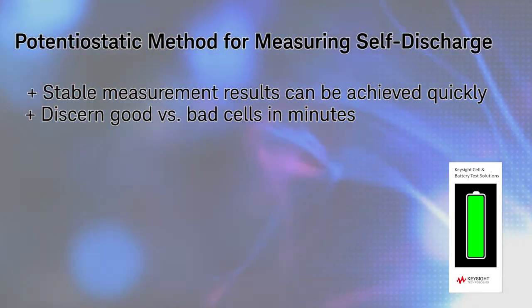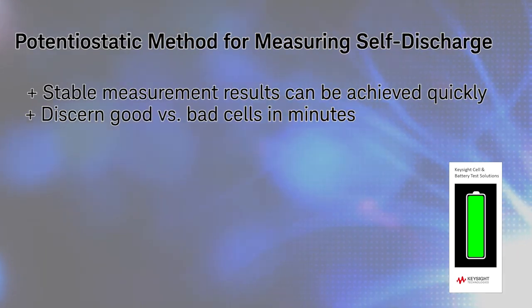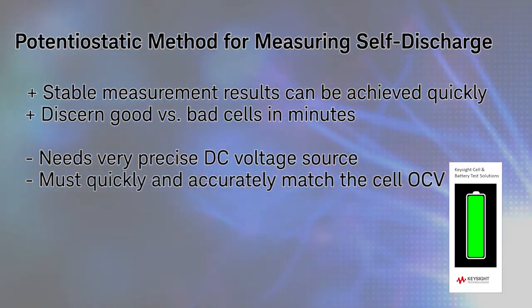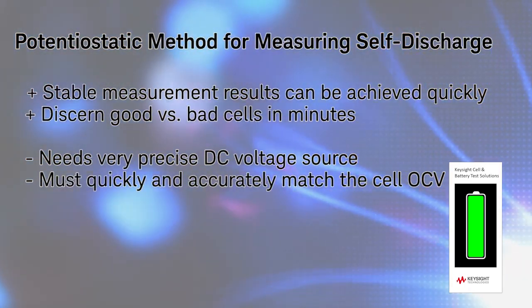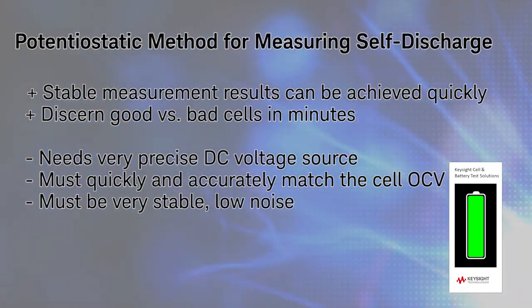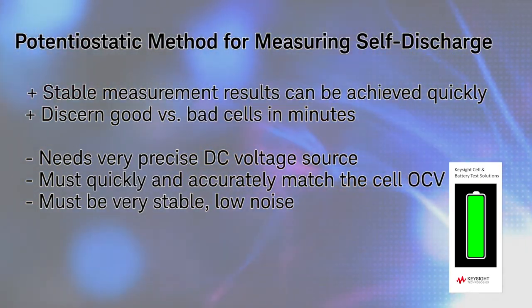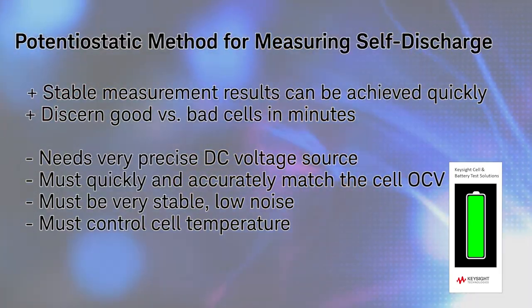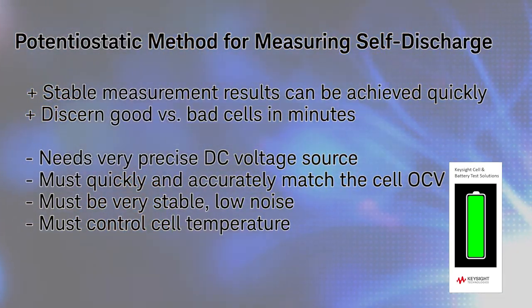The potentiostatic method requires precision equipment. The DC source must be very accurate, quickly match the cell's open circuit voltage, be very stable and have very low noise. You must also control the cell's temperature to prevent cell voltage variation caused by temperature changes.